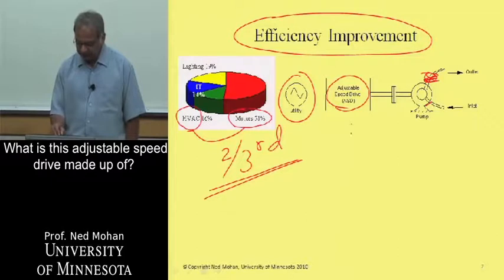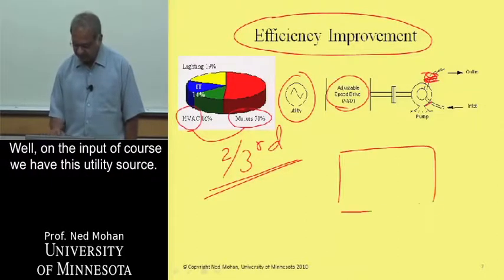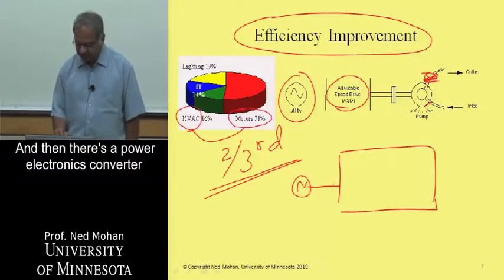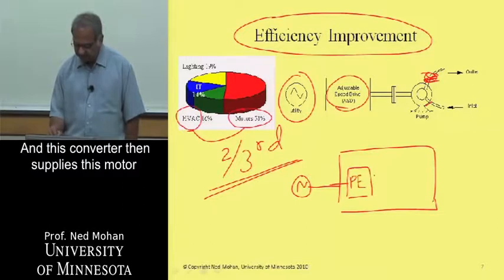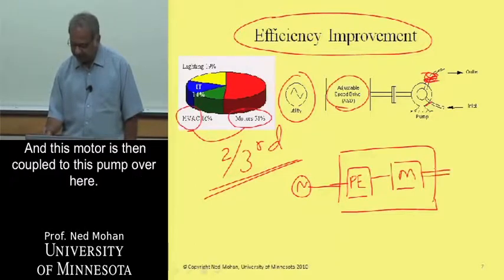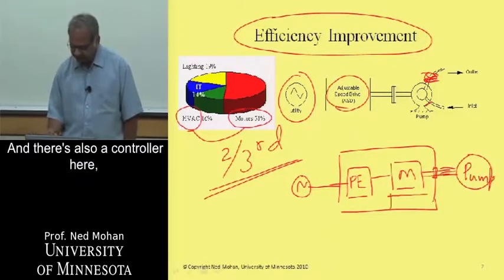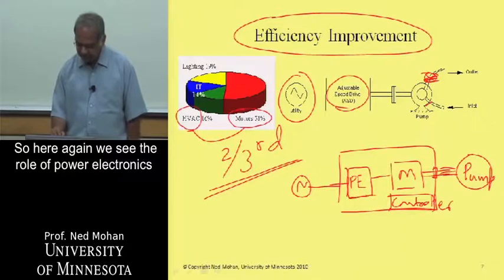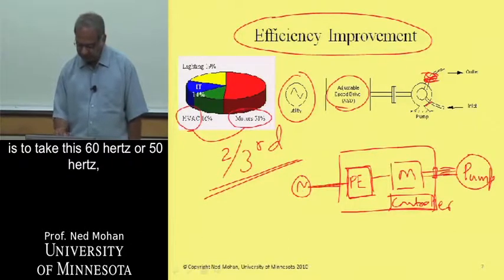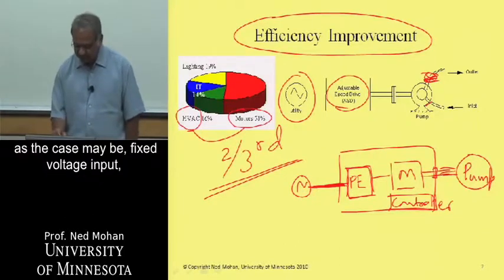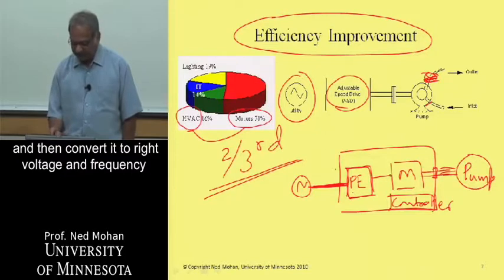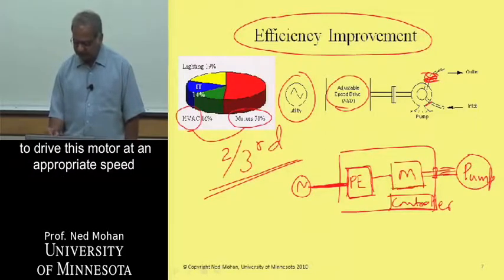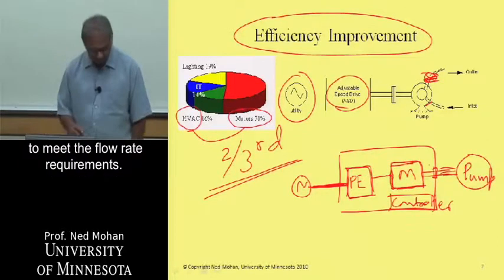What is this adjustable speed drive made up of? On the input we have the utility source, and then there's a power electronics converter which supplies the motor with appropriate voltages and frequencies. This motor is then coupled to the pump, and there is also a controller to control the whole system. The role of power electronics here is to take the 60 or 50 hertz fixed voltage input and convert it to the right voltage and frequency to drive this motor at an appropriate speed to meet the flow rate requirements.